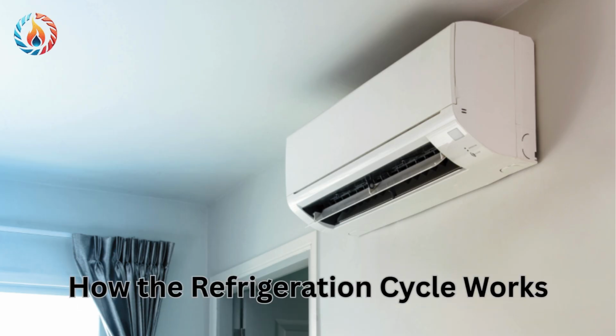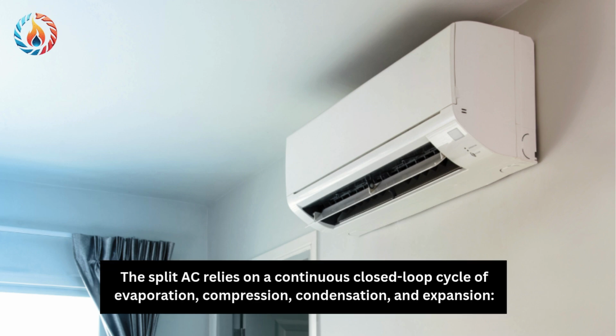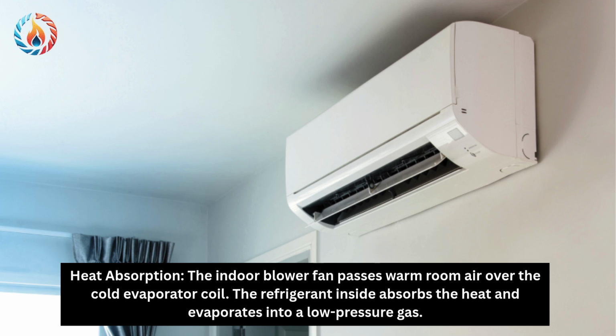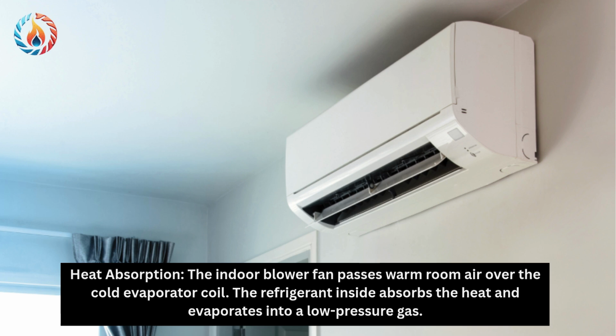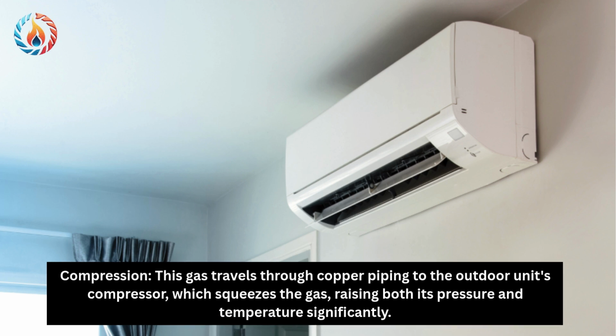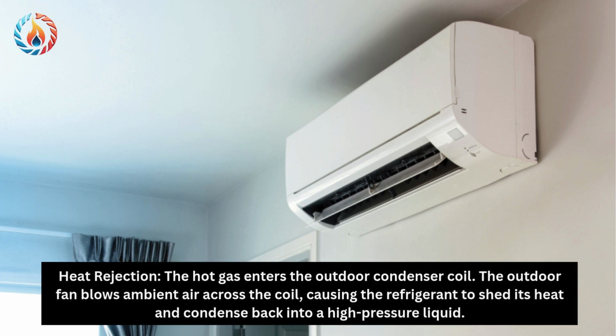How the refrigeration cycle works. The split AC relies on a continuous closed-loop cycle of evaporation, compression, condensation, and expansion. Heat absorption. The indoor blower fan passes warm room air over the cold evaporator coil. The refrigerant inside absorbs the heat and evaporates into a low-pressure gas. Compression. This gas travels through copper piping to the outdoor unit's compressor, which squeezes the gas, raising both its pressure and temperature significantly.